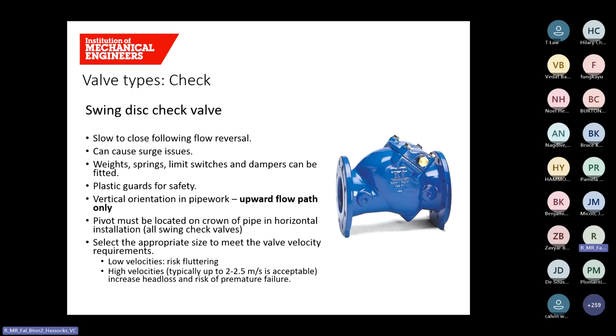The valve can be operated or positioned in vertical pipework or horizontal pipework, but it's really important to note that it can only be installed with the flow direction going up. So the valve opens in the upward position. If it's orientated facing downwards, then the valve may fail to close. Also, the pivot of the valve must be on the crown or the top of the pipe. And that's the case for all swing check valves.